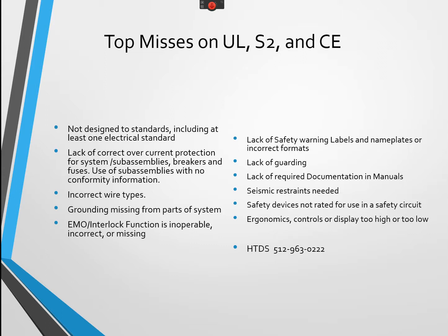Now, I talked about this next one, safety devices not rated for use in the safety circuit. Tough one. If you're using a relay for a safety circuit, it needs to be a safety rated relay. Now, under some standards, we can get around that by using a highly reliable relay, derating it, protecting it, and everything else, but that's a whole other bag of worms, and you might not get accepted anyway. So just use a safety rated device in your safety circuit. And we'll talk about safety PLCs and stuff like that later.